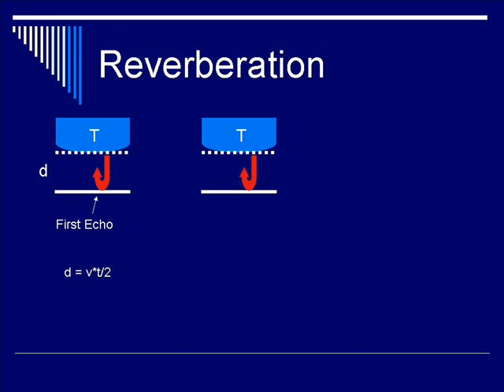This highly reflective surface reflects the echo back towards the transducer, which in turn suffers another reflection. Therefore, you have a second round trip of the ultrasound wave, albeit at a much smaller amplitude, that travels to the reflector and back. The two round trips lead to twice the propagation time, so the ultrasound machine places the reflector at distance d1 — which is 2 times the original distance d — explaining both the equal spacing between bands and the diminishing signal amplitude of this artifact.